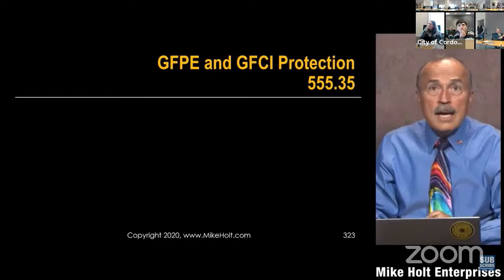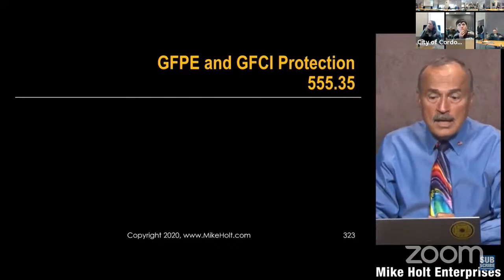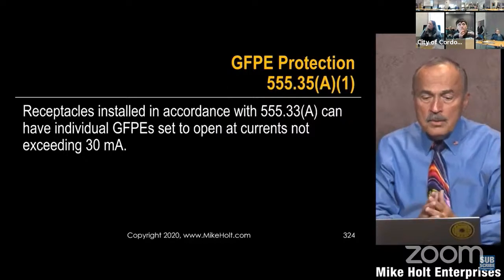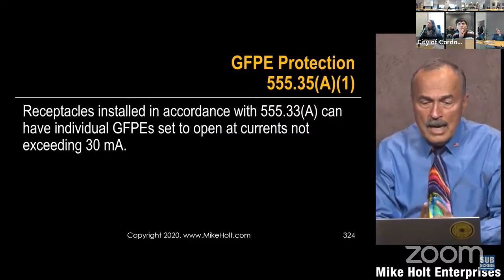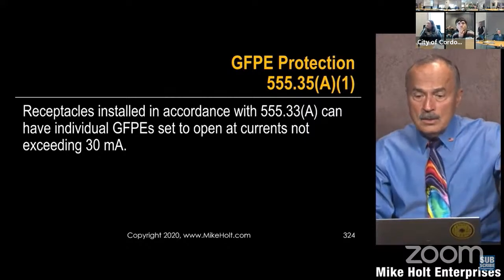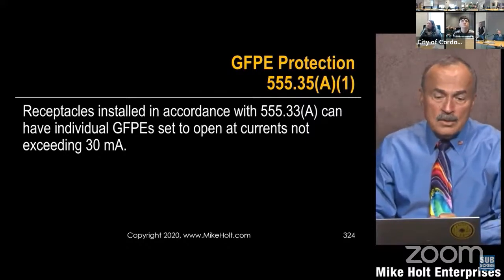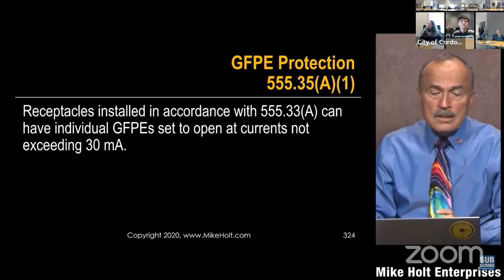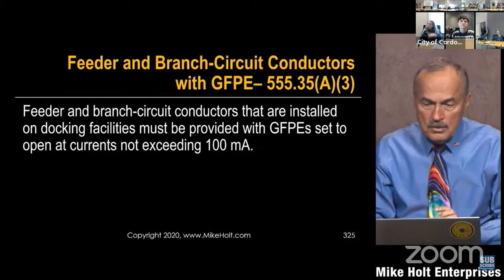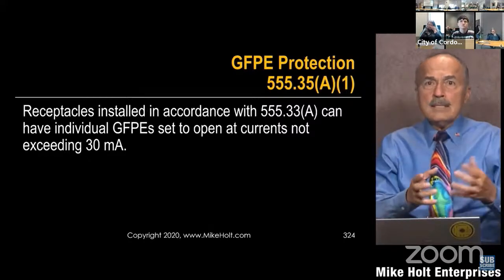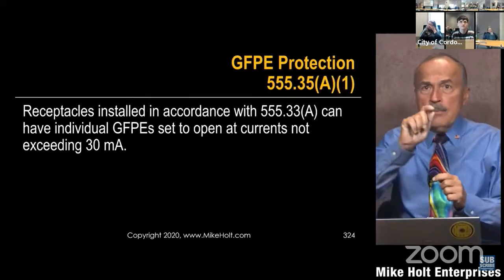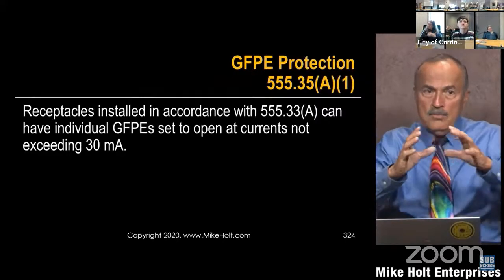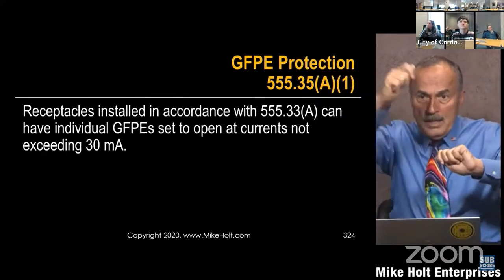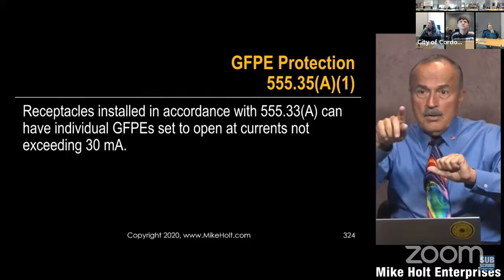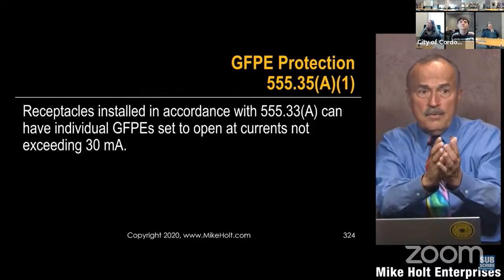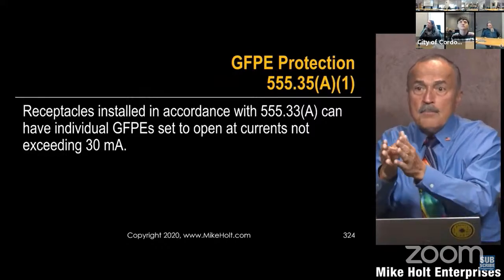GFCI, wait, GFPE and GFCI protection. Receptacles installed in accordance with 555.33(A), that's the shore power outlets, can have individual ground fault protection set to open at current not more than 30 milliamperes. I have a picture, don't have it. So in the shore power outlet, I like to get a picture of a shore power outlet right here. You have a breaker, and you get a picture of a breaker and a receptacle. So if you open the shore power outlet, a little pedestal, and you open it up, you're going to see that there's going to be a 50 amp breaker, and it's going to be a 20 amp breaker, and it's going to be a twist lock 50 amp receptacle, and it's going to be a 20 amp receptacle.